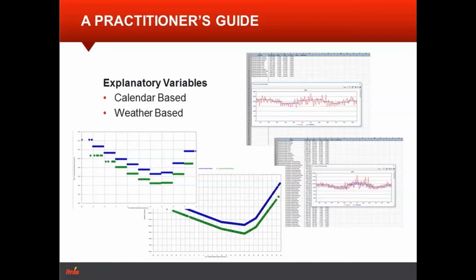We introduce all of that, and then you can introduce lag loads on top of all of it. So your models break down into calendar-based variables that impact the intercept, shifting the loads up or down depending on the day of the week or the season or holidays. Then variables that are weather dependent, so how loads move, like that scatter plot relative to weather. And then at the end, you would introduce any lag terms if you're doing very short-term forecasts.